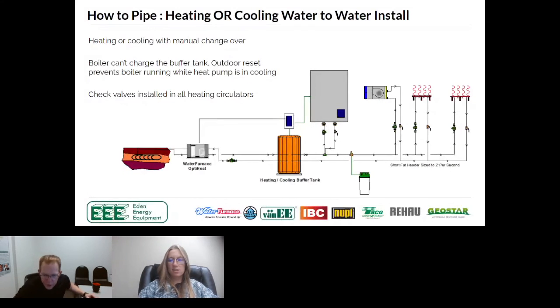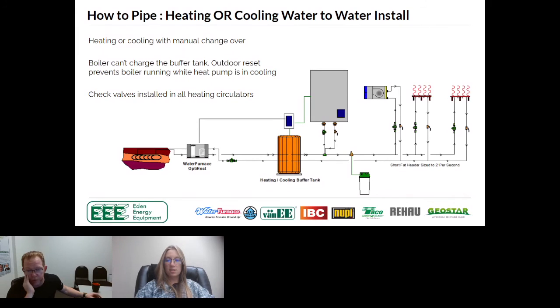So in this scenario, what would end up happening is your air to water, it doesn't matter whether it's Water Furnace or somebody else's brand, is going to heat this tank to 120 degrees. And this 120 degrees can probably take care of everything in this house. In your scenario, you've got 3/4 inch copper fin tube out in the house, and we know it needs 180.